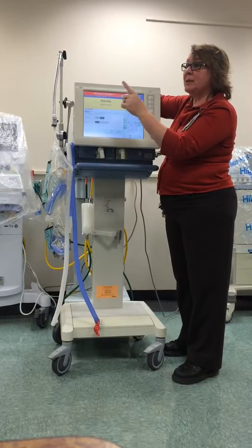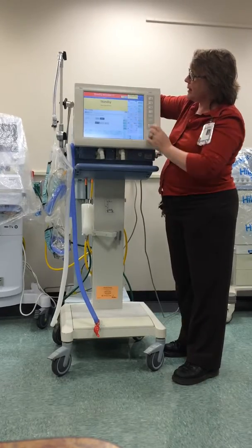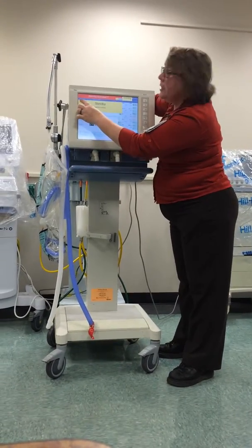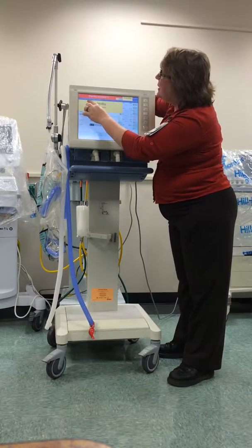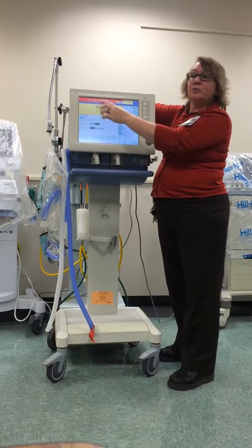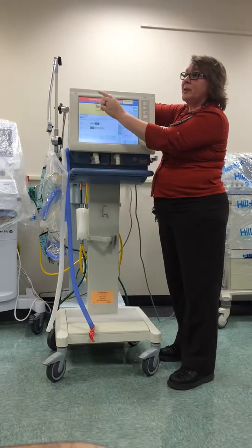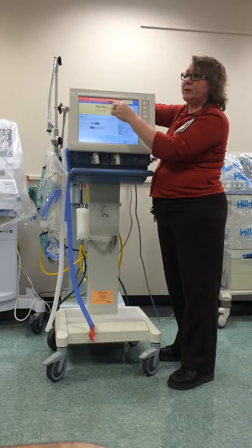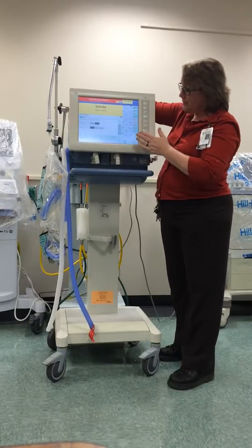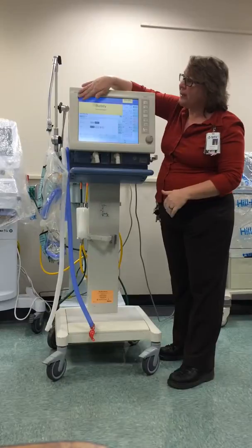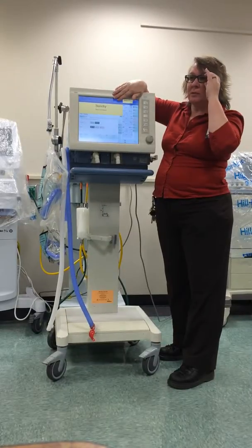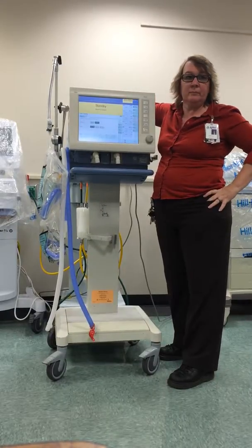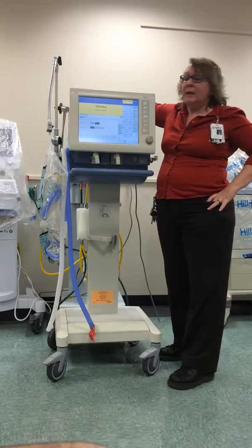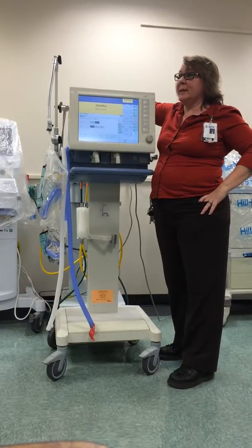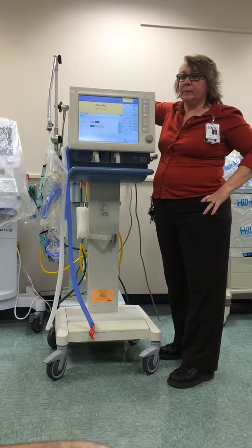So to actually put it in standby, alarm reset, and it tells you that up here: confirm standby, touch alarm reset, and continue. So this one, like some of the other ones, tells you what to do, but it's in a different spot. It's up here in the blue. So alarm reset, confirm. You want it to be all blue at the top. Now it's in real standby mode. It must be in standby just like any other vent to do the calibration.